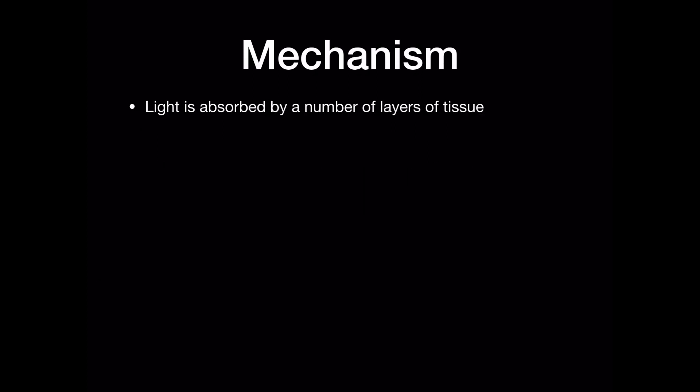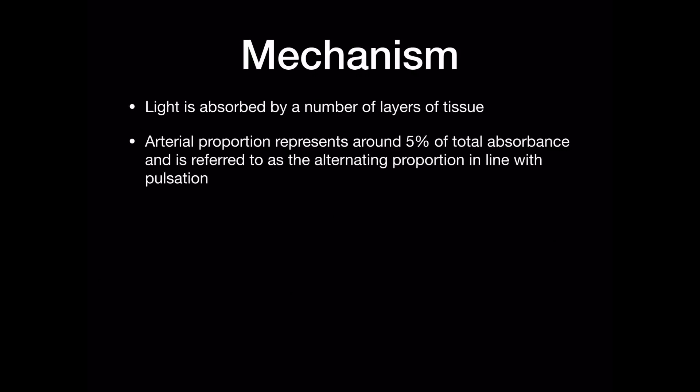Light is absorbed by a number of layers of tissue. The arterial proportion represents around 5% of total absorbance and is referred to as the alternating proportion in line with pulsation. The photodetector is able to generate a voltage dependent on the amount of light it receives.